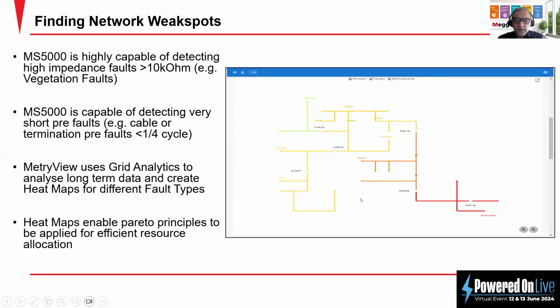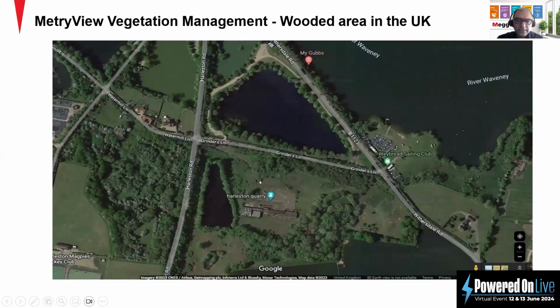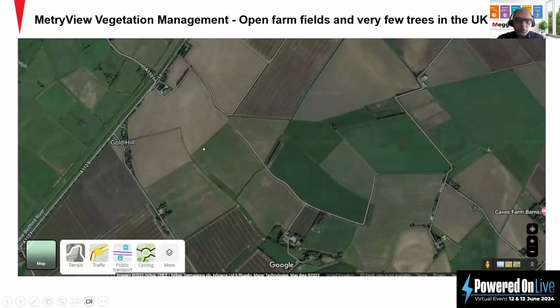You can use the fault data for finding the weakest spot, and it gives you the analytics for a period of time, showing which parts of the network have the most faults and which parts need more investigation. And it's able to detect very short faults, like in cable termination and installation, and other types of faults. This is an example installed at one UK utility, using the network for vegetation problems. The sensors were installed in a wooded area in the UK, and another set was installed in open farm fields with very few trees.